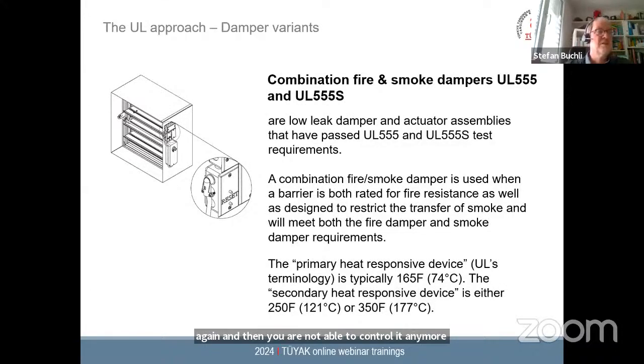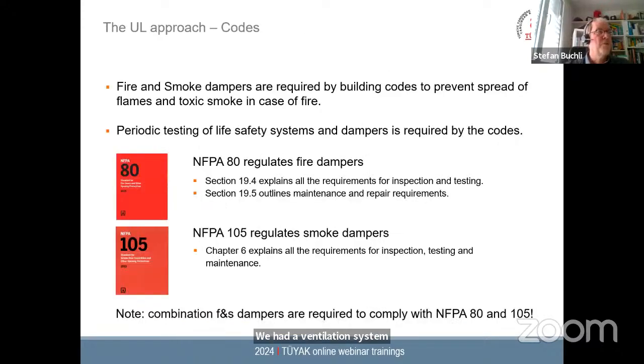So in initial state, the fire brigade could operate this damper, let's say for trying to clear some smoke via the ventilation system. If we look at the standards, there are also NFPA standards in place. There is mainly the NFPA 80 regulates the fire dampers. It explains the requirements regarding inspection and testing, and it outlines as well the maintenance and repair requirements. You can find the same for smoke dampers, which is NFPA 105. It explains also the inspection, testing, and maintenance requirements. And of course, for the combination fire smoke dampers, you have to comply with both the above standards.